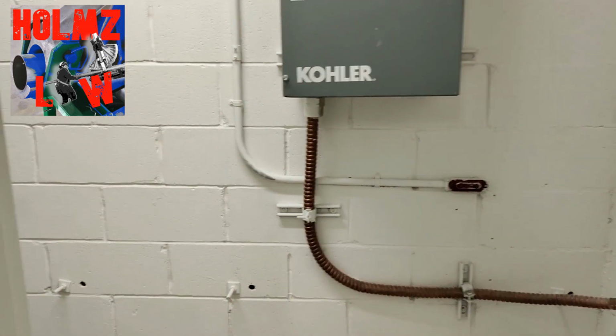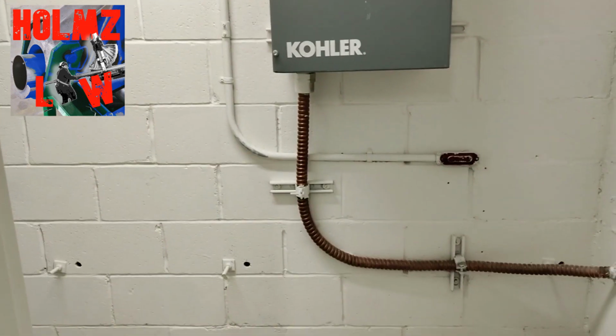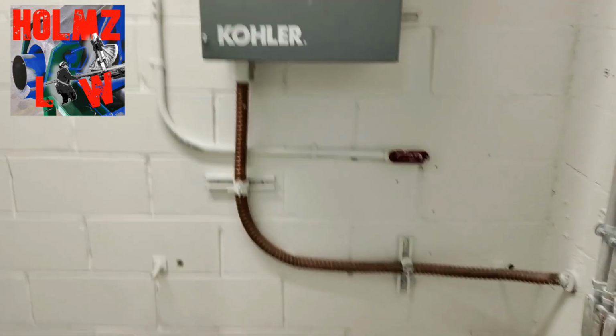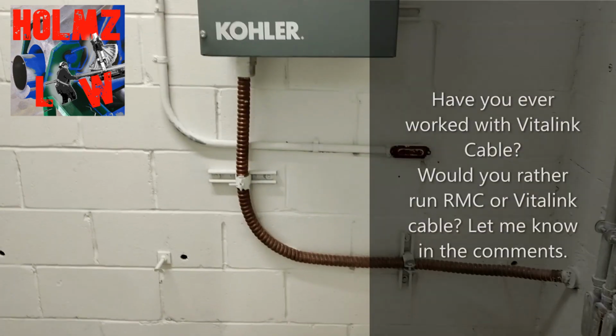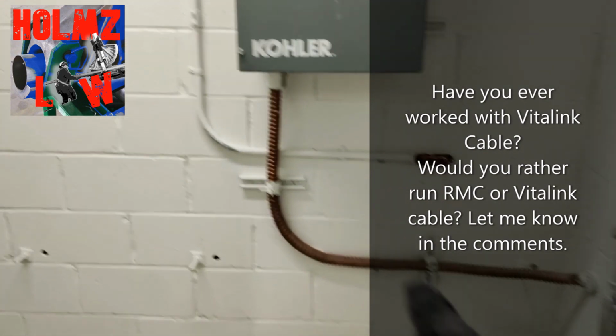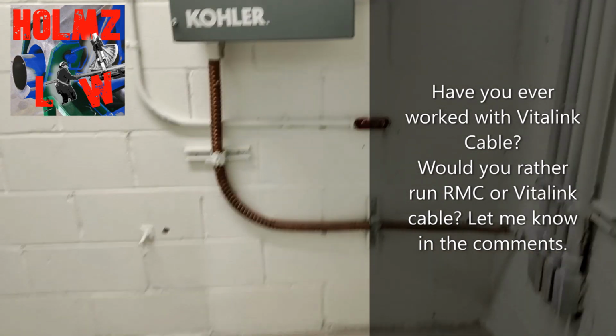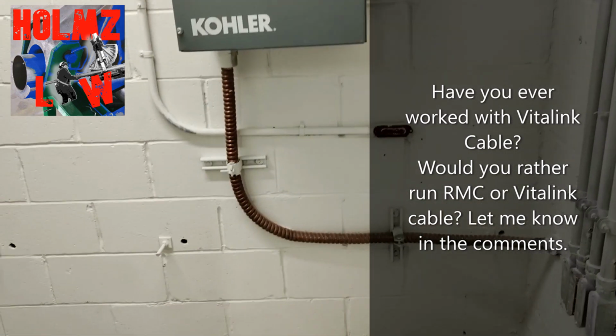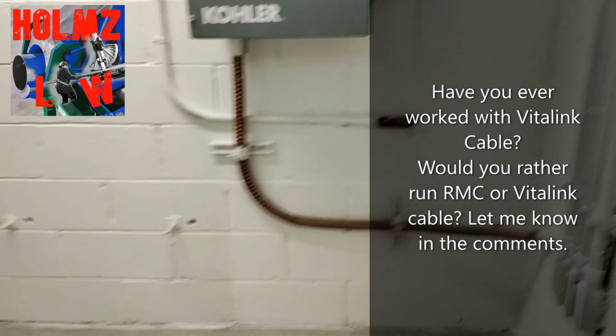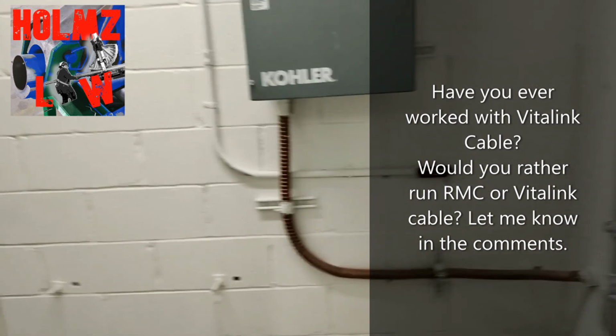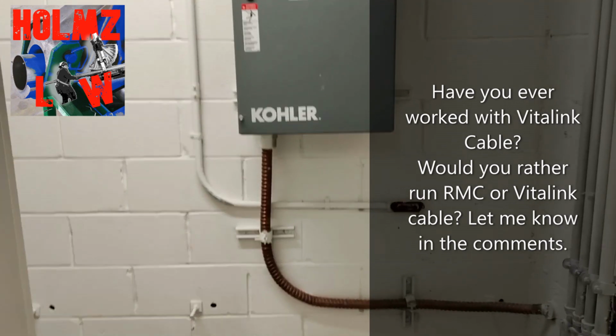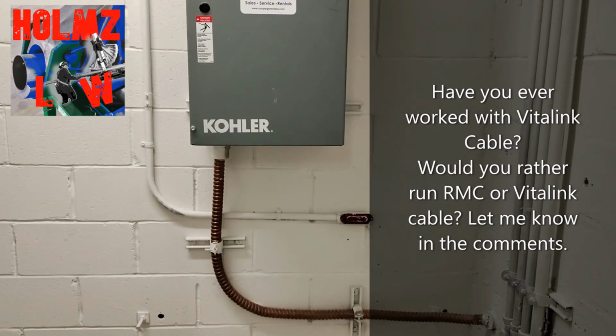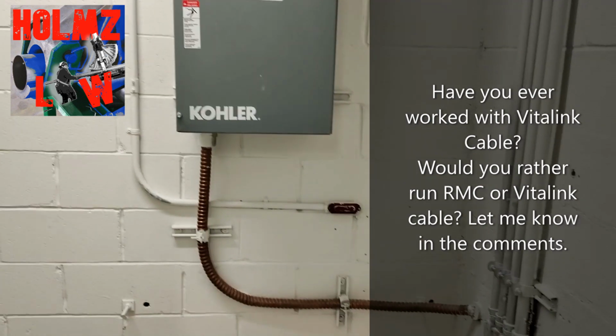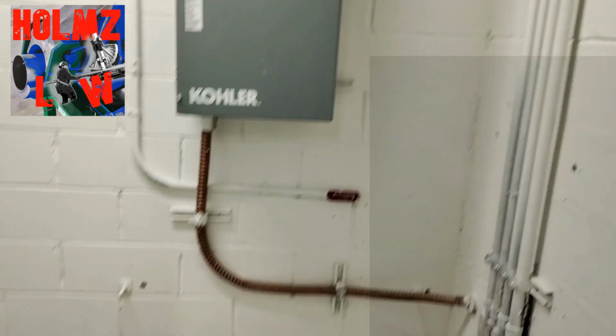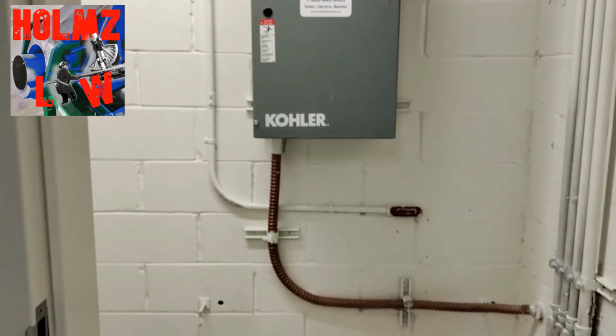A Vitalink was run to it. Honestly, I'm still on the fence about whether I like this stuff. I think I'd rather run some rigid conduit. This metal sheathing kind of cracks really easily, so you have to be really careful when running it, and it takes more time because of that. It cracks so easily, and if you crack it, you're actually cracking the equipment ground, which isn't good. Then you'd have to put a splice box somewhere, which is just more work. Okay, so that's it for that.